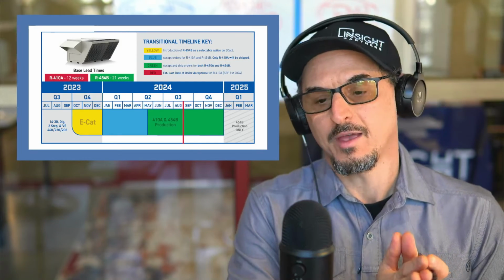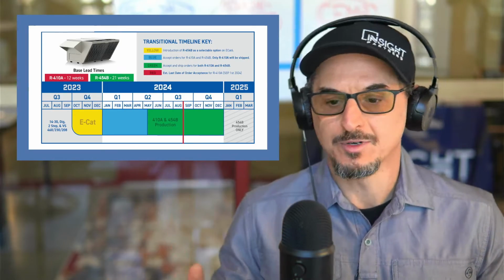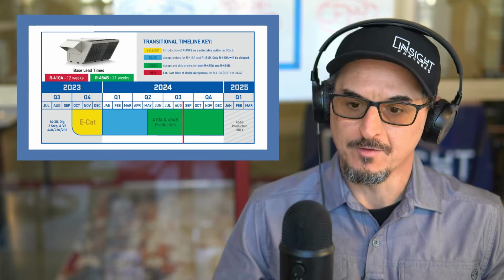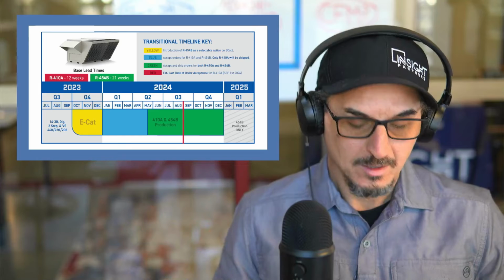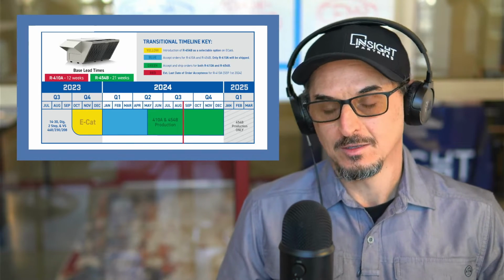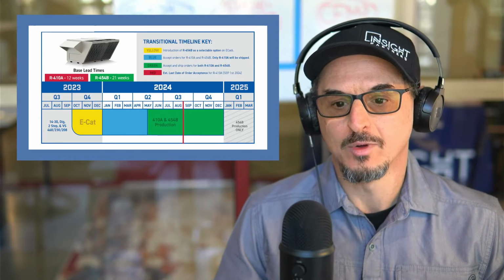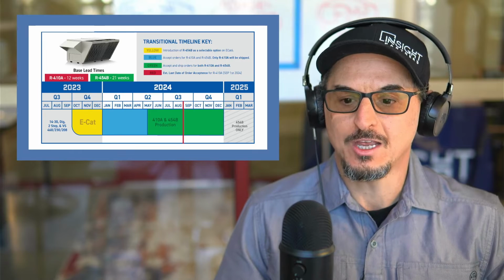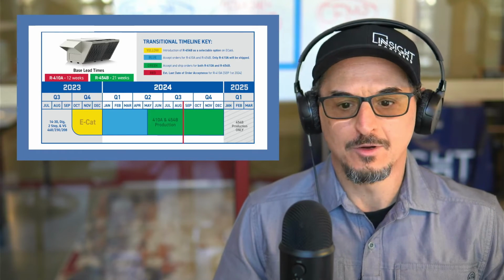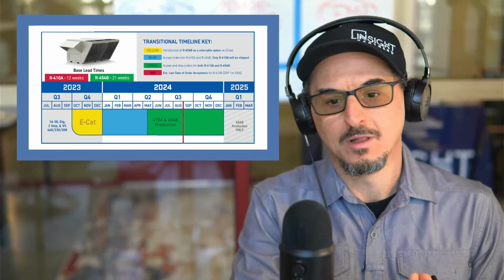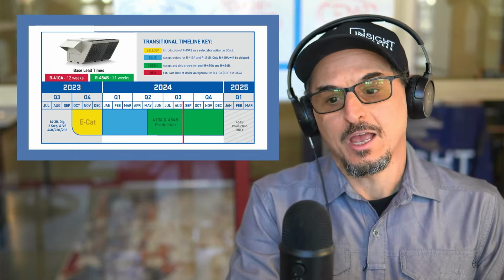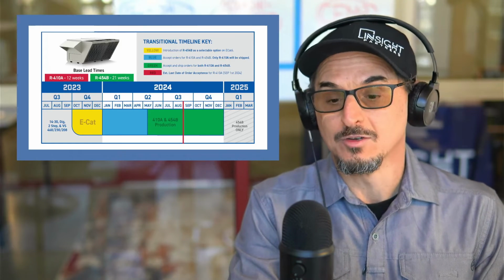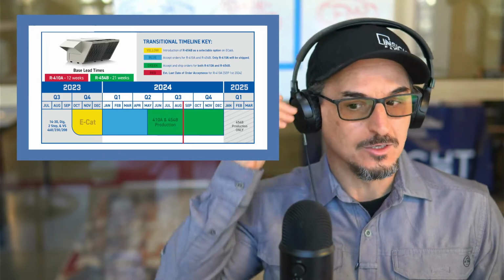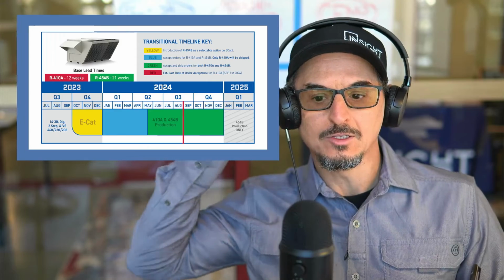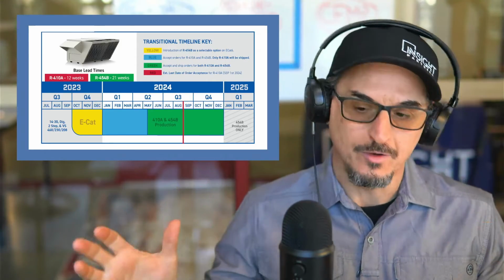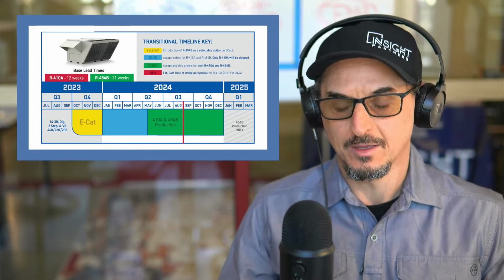In terms of manufacturing, this is meant to represent a typical schedule from one of our manufacturers. Don't take this as gospel for your manufacturers - please call, recall, and continue to call and talk to your local reps, because it'll be different for every manufacturer. What you're seeing here represents a pretty good idea of what's going on. You could select and order R454B equipment now. If you're specifying a job that's not going to ship very soon, you probably want to look at specifying it with 32 or 454B, because it is a different machine - a totally different UL rating required, a different selection. So I would say change that now.